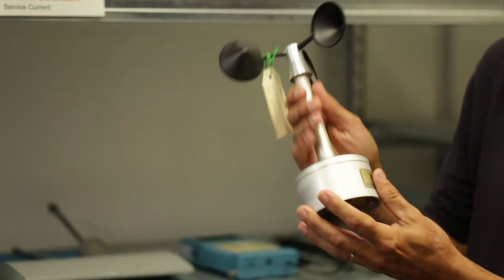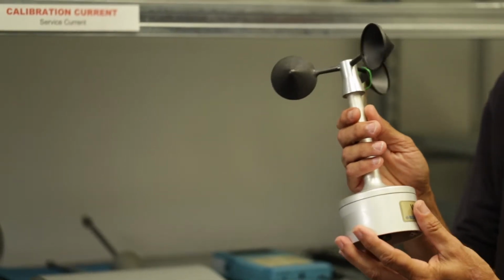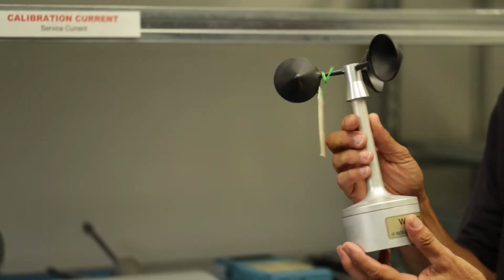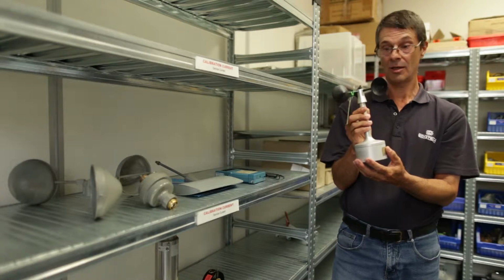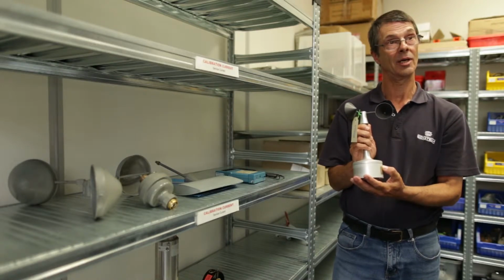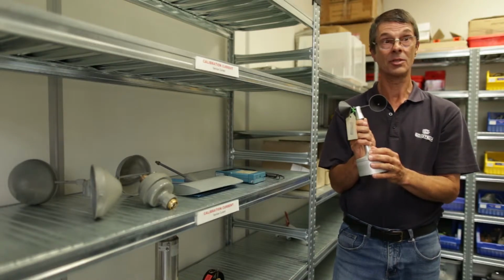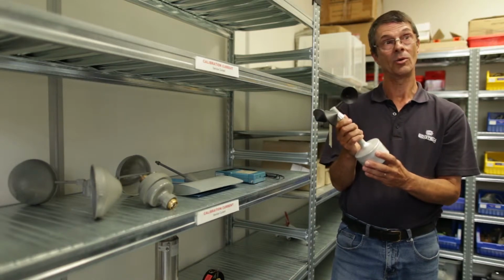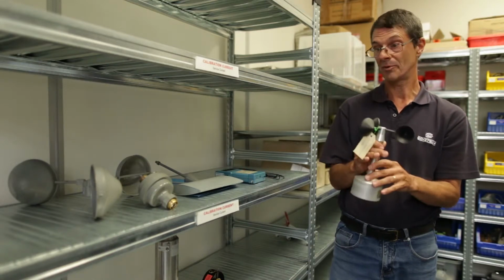We have customers as far away as Jakarta in Indonesia. Their Bureau of Meteorology sends us their cup anemometer once a year to calibrate. They then use that as a transfer standard to calibrate all their other anemometers, so that's a critical application from their point of view.